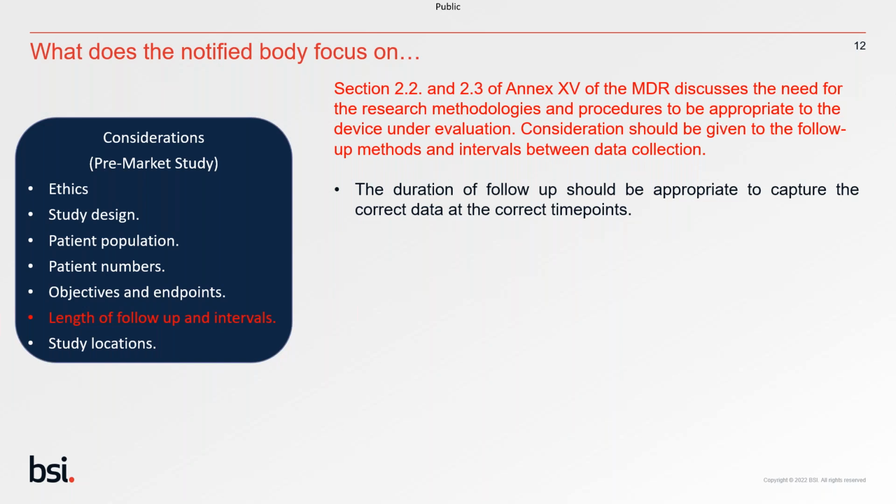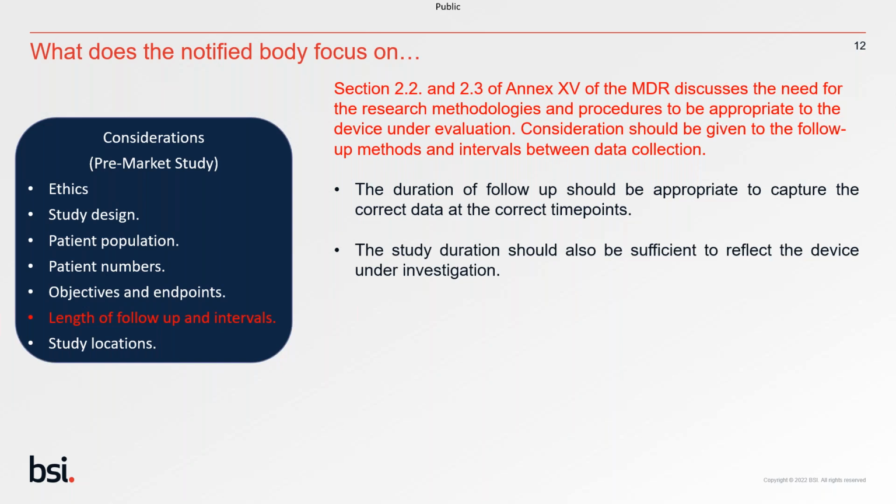One of the things that we often see is that the duration of follow-up in a study is often looking at safety, and it's focused, and rightly so, but people often forget what the performance points are at that follow-up as well. So really make sure that when you're documenting that, you explain why you have chosen those follow-up methods, and what you are looking for at that point in terms of safety, but also performance from the device. Ultimately you need to prove that the performance either increases or remains the same throughout the duration, or where there is a reduction in performance, which can typically happen with certain devices, is that expected and is that justified? So really consideration in the documentation there.